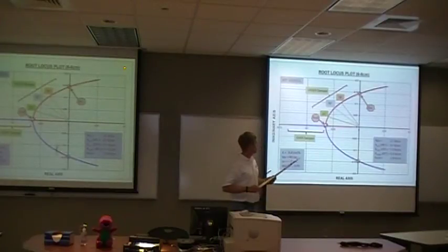We have the 45-degree angle, which is the 1/500th decay, with a controller gain of 3.5% per centimeter, and then the 70 degree is the 1/10 decay at a controller gain of 7.2% per centimeter, and the 78 degrees is quarter decay, which is 10% per centimeter, and then the ultimate controller gain is 15. And then we have an overdamped region right here, and the underdamped region is up there.